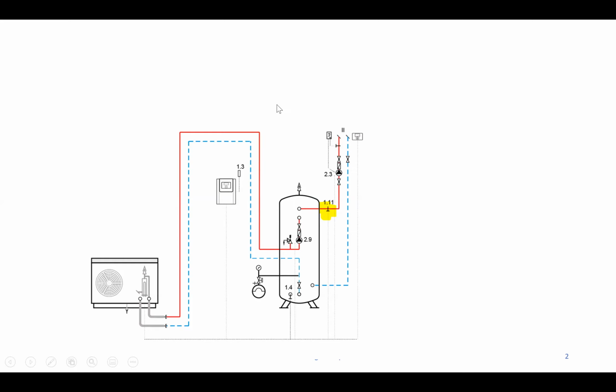But if you want to do it, you can do it. So you can have the heat pump hitting the buffer tank, like I've mentioned, and coming out of the buffer tank, you can have it running into a manifold if you like, and you can have 5 heating circuits, all controlled by thermostats dotted around somebody's house. The thermostats can control the pumps and then send a signal back to the WPM to start our system. Very simple, can be done.